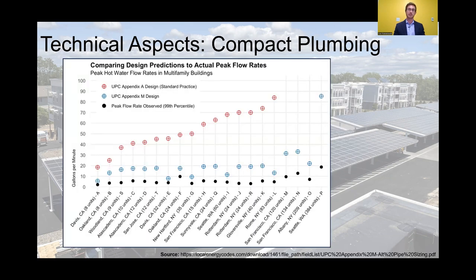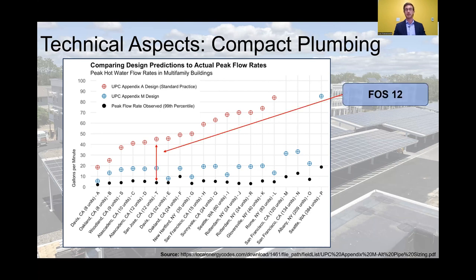What is compact plumbing? Well, in the red line here, we can see the Hunter curve. The Hunter curve was created in 1940, and believe it or not, we still use a lot of those standards for plumbing today when we're sizing our pipes. Keep in mind, the Hunter curve was actually created based on experiments done in the 1880s for galvanized steel pipe. We don't use galvanized steel pipe anymore. And that's why you get a factor of safety between measured flow rate data and the Hunter curve of around 12.